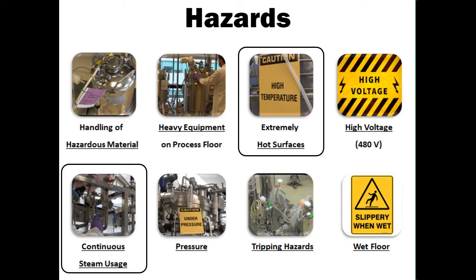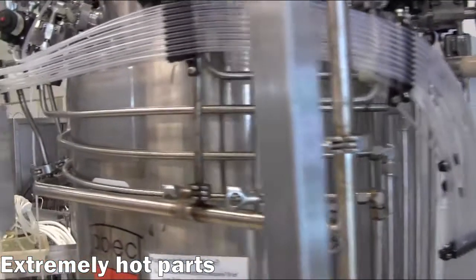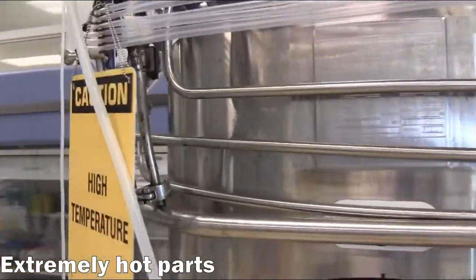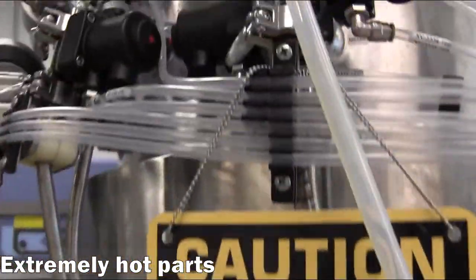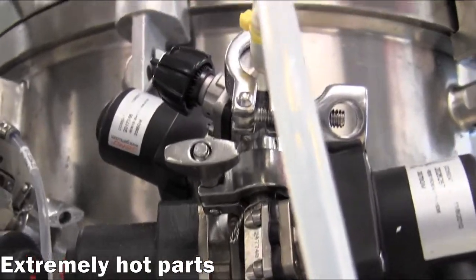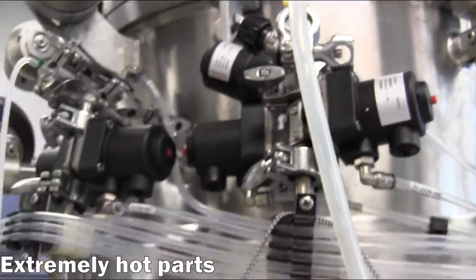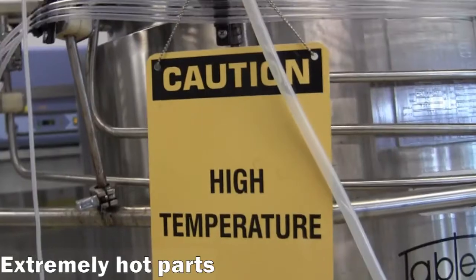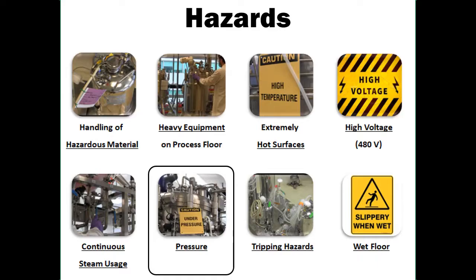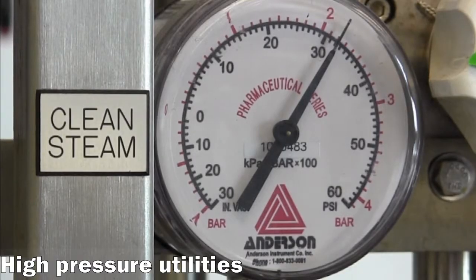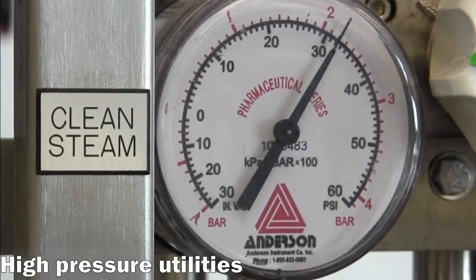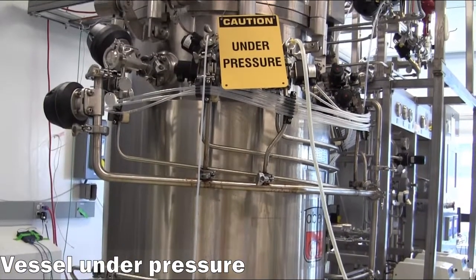Another hazard associated with operating the ABEC reactors is the hot surfaces created by continuous steam use. Steam lines run throughout the ABEC skid, through the pipes surrounding the bioreactor, and around the addition port connections. When steam is actively running through these lines, a high temperature sign should be posted on the reactor and caution should be taken when using hand valves. Steam, along with the air and water, also contribute to pressure hazards. All these utilities are provided at around 30 psi and the vessel is pressurized during operation.